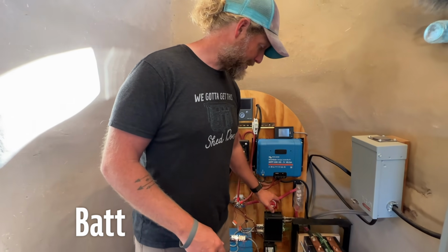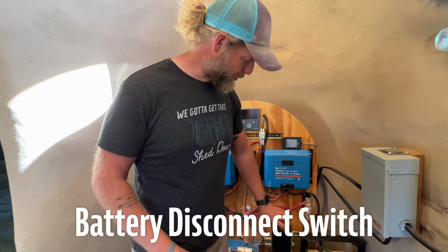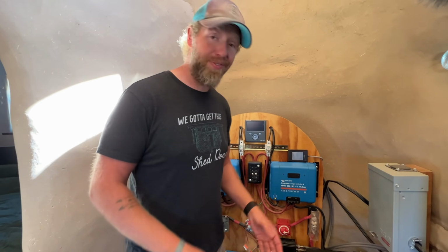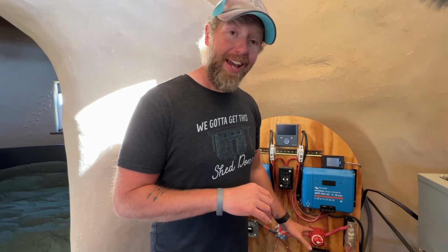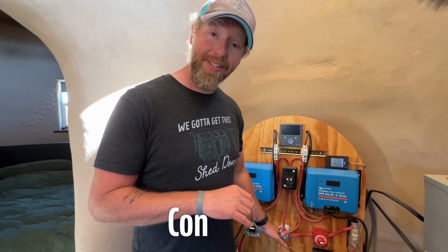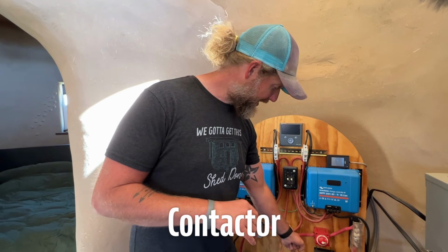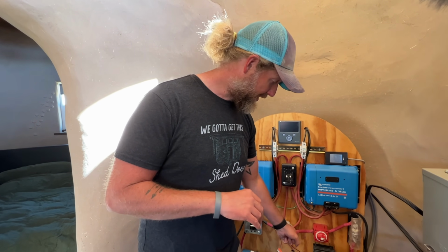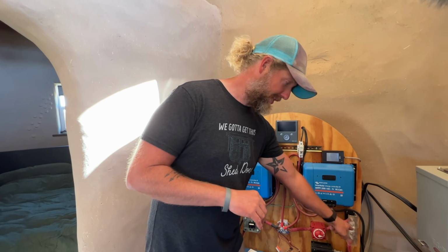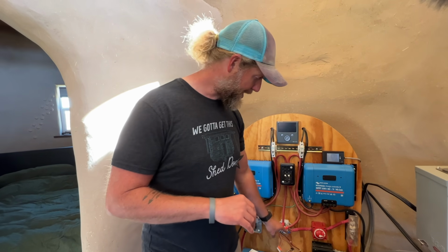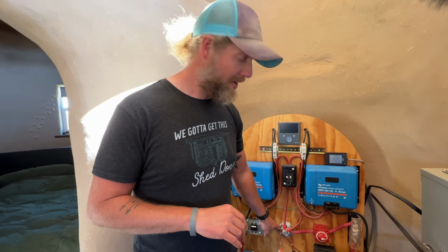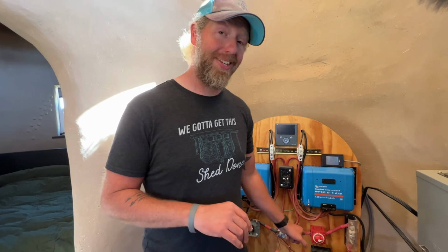There's also a battery disconnect, and this is a switch that will cut off any power from the batteries if you need to do any maintenance or anything like that. After the switch, you're going to run through your contactor. Everything on this side of the contactor is always going to have power unless this blows or you turn this off. But everything on this side of the contactor will only have power if the BMS says it's okay for it to. It's checking for voltage and temperature and all sorts of things.